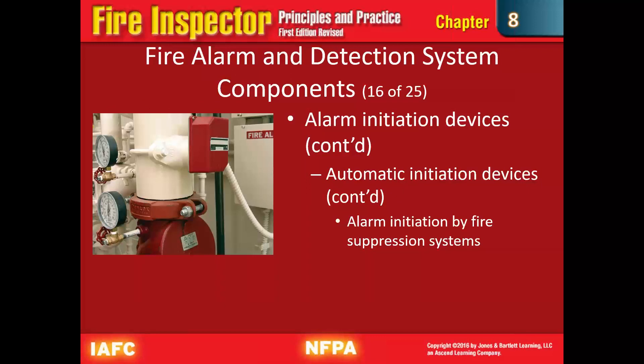Alarm initiation devices are also included on sprinkler risers. You can see a red box at the valve — it detects the flow of water. Many of those systems have a small paddle or fan blade inside that starts turning when it detects water movement, indicating that a sprinkler head has activated and water is flowing somewhere, which triggers an alert.